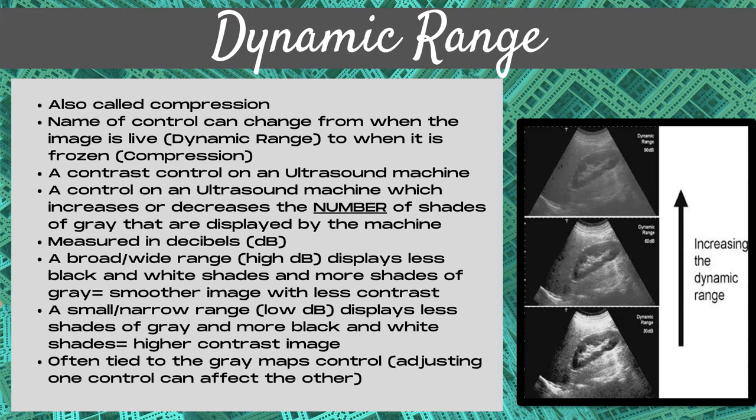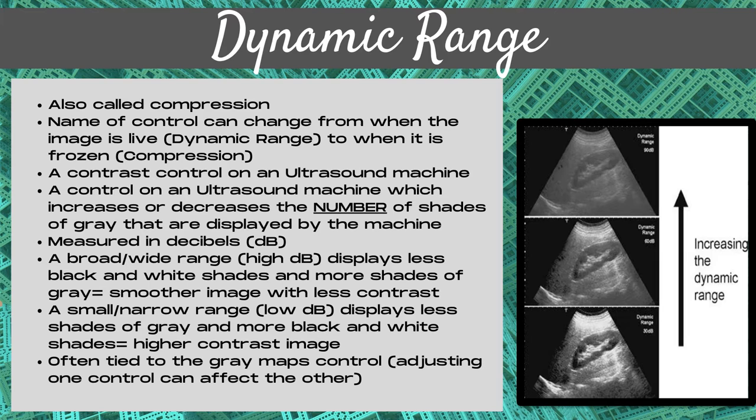Let's discuss the dynamic range control on an ultrasound machine. The dynamic range control is a contrast control on an ultrasound machine, and it's also called compression. On some ultrasound machines, the name of this control can change — from when the image is live, when it's called dynamic range, to when it's frozen, when it turns into the name compression.